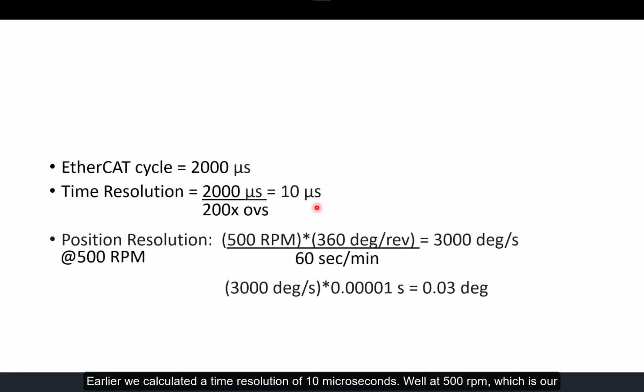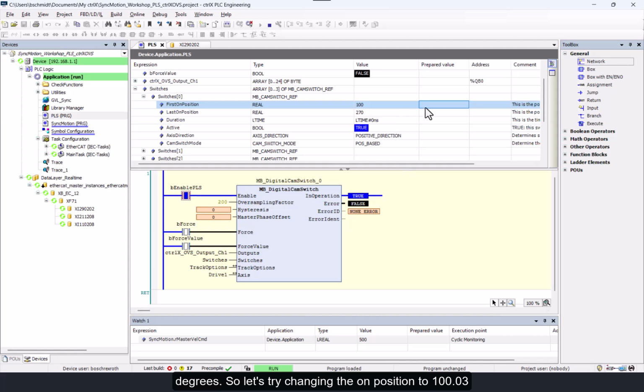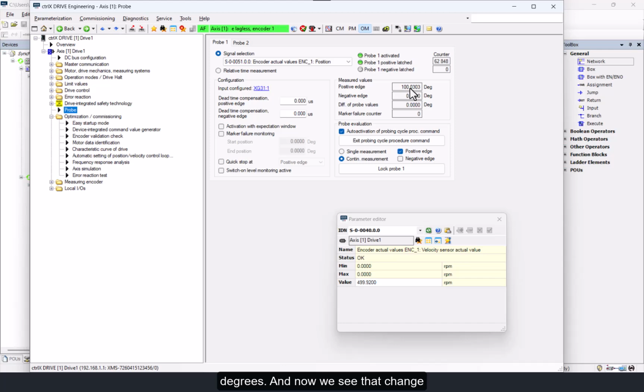Earlier we calculated a time resolution of 10 microseconds. Well, at 500 RPM, which is our current velocity, that converts to a velocity of 3,000 degrees per second. And if we multiply 3,000 degrees per second times 10 microseconds, we get a resolution of 0.03 degrees. So let's try changing the on position to 100.03 degrees. And now we see that change reflected in the captured position.